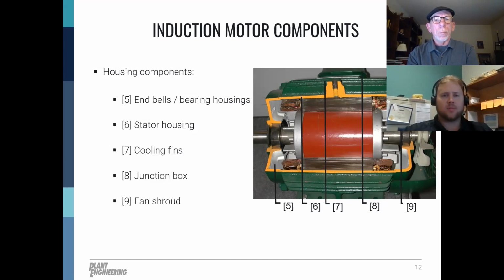Here we have the housing components. The end bells are on both sides of the machine, the bearing housings and the stator housing, which you'll see here painted orange. And then there are cooling fins on the outside of the case of the motor. The cooling fins basically give the cooling portion of the motor more surface area to keep cool, for heat to dissipate during operation. Then you'll see the junction box. That's where the terminals are found. We're going to be talking a lot about the electrical side of the motor in this presentation, especially later on. And then finally, you see the fan shroud. The fan shroud is used to safely guard the fan during operation.